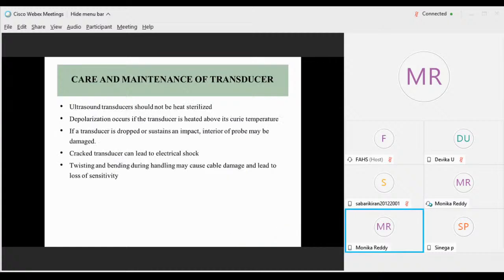So, care and maintenance of a transducer. Maintenance of the transducer is a must, and you should be well aware of it so that no mishandling will happen. The ultrasound transducer should not be heated with sterilization techniques. We are not supposed to use heat sterilization for transducers, and depolarization occurs if it is heated above the Curie temperature.